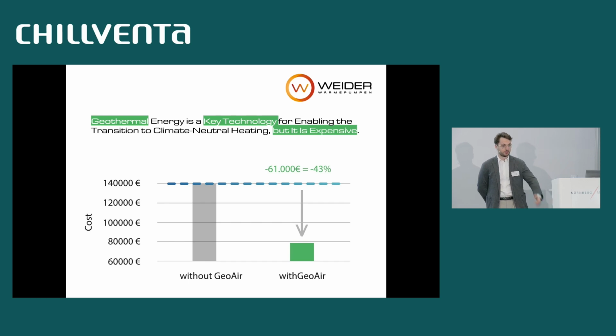First, I want to present the main results of the geoAir before talking about the innovation itself. So we implemented the geoAir at a big project in Austria, in Vorarlberg, where initially a geothermal heat pump was planned, and the initial planning cost just for the probes itself was 150,000 euros. Through the use of the geoAir, the investment cost for the geothermal source could be reduced by 60,000 euros in this case. And the high cost for the source is usually a problem for geothermal heat pumps for larger use.